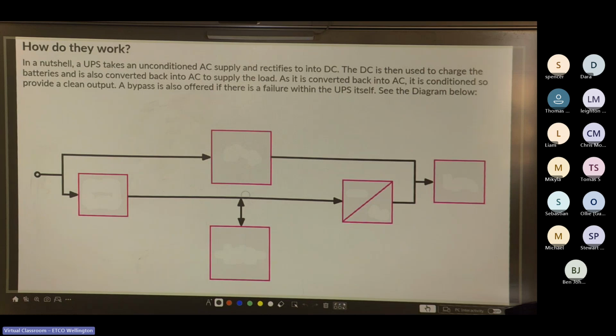Cool. So how do they work? In a nutshell, a UPS takes an unconditioned AC supply and rectifies it into DC. The DC is then used to charge the batteries and also converted back into AC to supply the load. As it's converted back into AC, it is conditioned so it provides a clean output. A bypass is also offered if there is a failure with the UPS itself.